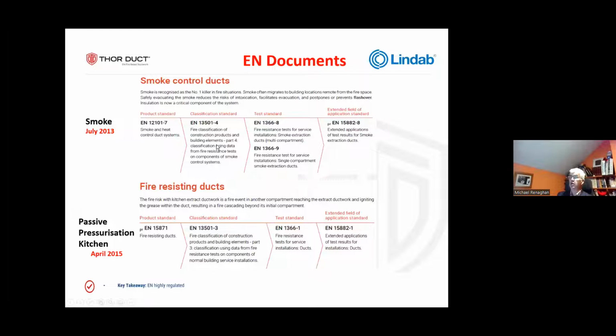if you want to do something outside of the test, the extended field allows you. For smoke, there are certain limitations. The maximum size is 1250 by 1000. That's it. So under EN, you can't go bigger than that. And the reason for that is that the testing required for bigger sizes is all about leakage. And it's not easy to mathematically calculate it for larger ducts. As well as that, the volume of air required from a furnace during a fire to mimic 1100 degrees or 1000 degrees is a significant amount of energy and a significant amount of air. So regulating that so that you can measure the leakage is really, really problematic. So it's a problem. It's not possible at this stage. But for fire-resisting ducts, because it's not about leakage, it's about performance in different ways, both insulation and integrity, you can go up to 2.5 meters by 1250 under the extended field of application.